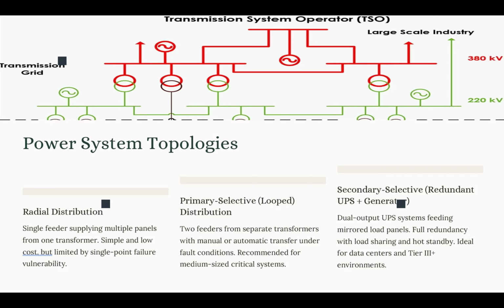The third topology is secondary selective topology, in which we have a redundant UPS plus a generator. Now, in that topology, we have a fully redundant dual power source, which normally works in a parallel or hot standby situation. Now, it has the highest reliability. There are tiers defined for reliability. You can search on that, and there's a standard for that. Secondary selective normally provides tier 3 plus or even tier 4 reliability, which is very good for data centers.